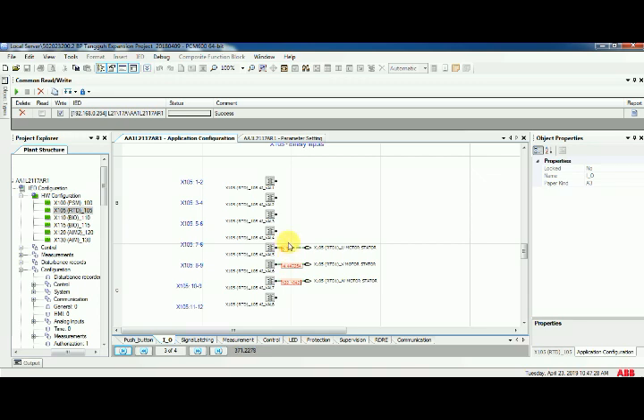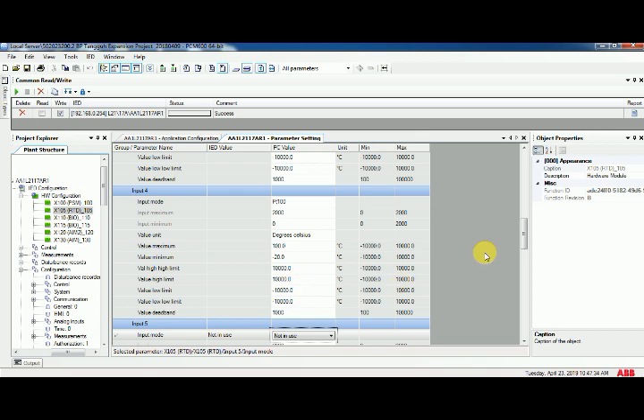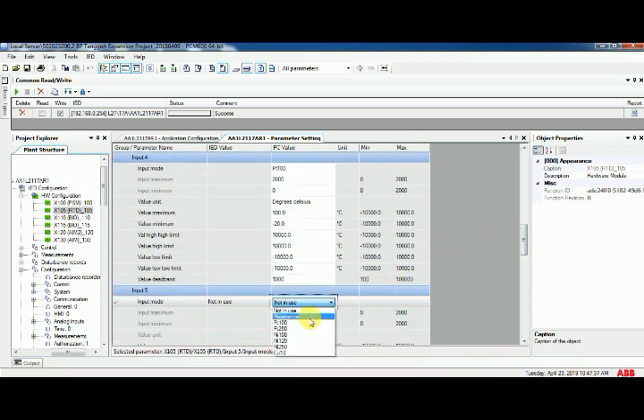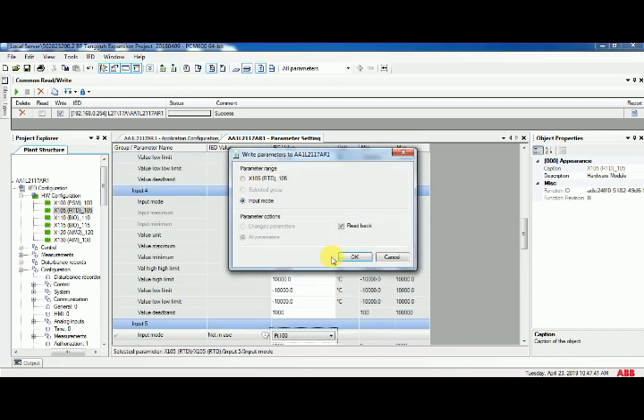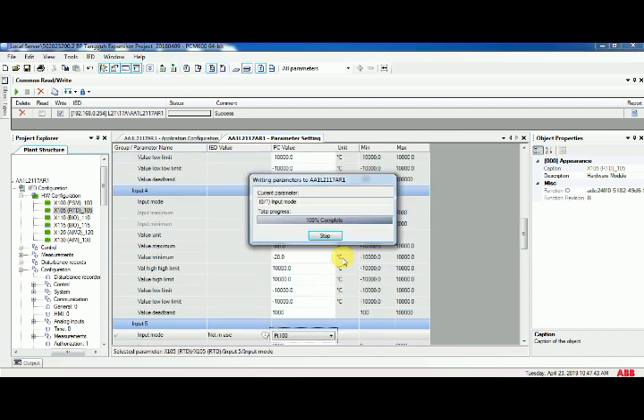For better understanding, I have taken the relay in work online. You can notice for winding U, temperature is not showing. I'm going to check it in the parameter. I noticed input 5 is off, so it is not showing. I enabled it and wrote it to the relay.